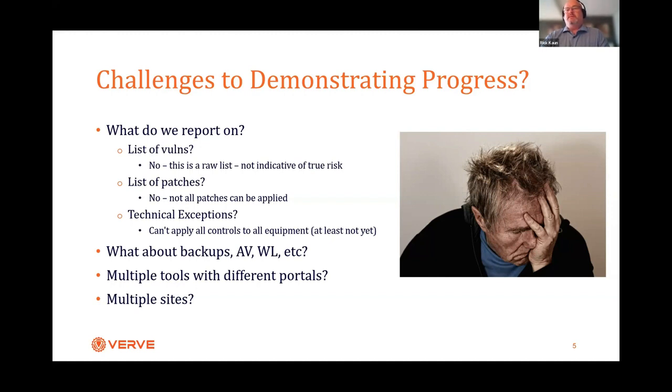There are lots of nuances in vulnerabilities, like attack vector. If it's a physical attack vector and you are completely locked up, or your substation's on the side of a mountain, maybe that's not an issue. Similarly with devices in a segmented network, network-based attack vectors have to go through multiple layers, and so maybe it's not as critical as a raw score as determined by researchers in a lab with no context of your environment.